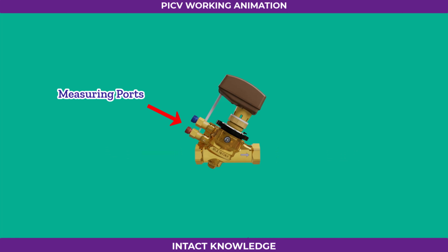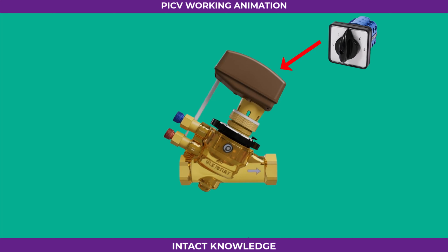This small port here is the measuring point. It's used to check water pressure with a manual gauge. Inside the valve, there's a stem that connects to a spring, allowing vertical movement up and down. On top of the PICV, an actuator is mounted to the stem. It's responsible for controlling that movement. The actuator also includes a manual adjustment knob, letting you operate the valve manually when needed.